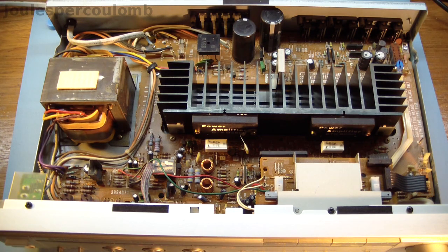Sometimes I've wondered whether it would be worth making a main safety earth connection to the chassis of devices like this. Of course, depending on the nature of the connected audio sources and how they're connected, this can sometimes lead to the pickup of unwanted noise. But if a bit of care is given to how the devices are connected, this problem can usually be avoided. A possible compromise might be to connect the protective earth to the chassis via a resistor. If the value of the resistor is selected carefully, it should avoid the noise problem, but yet might still allow for sufficient current to flow to earth in the case of a fault to blow the fuse, and certainly it would operate an RCD unit.